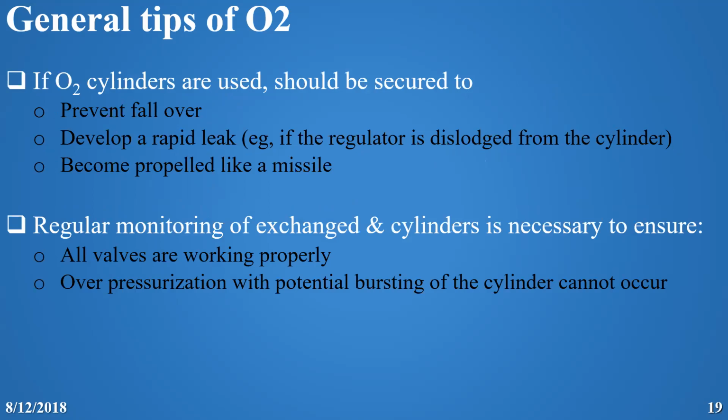If you use an oxygen cylinder, first prevent it from falling, check for leaks, because if there is a leak, it can propel like a missile. It moves so fast and it can kill anybody. The cylinder, the regulator, and the gauge should be checked every day to prevent possible accidents.